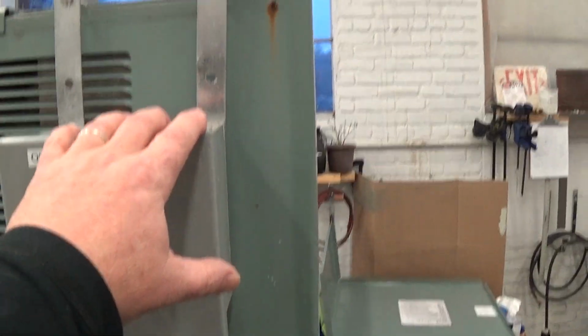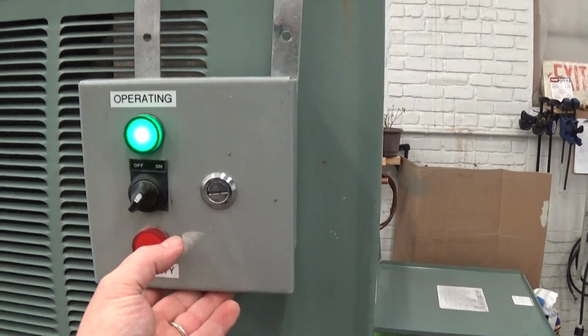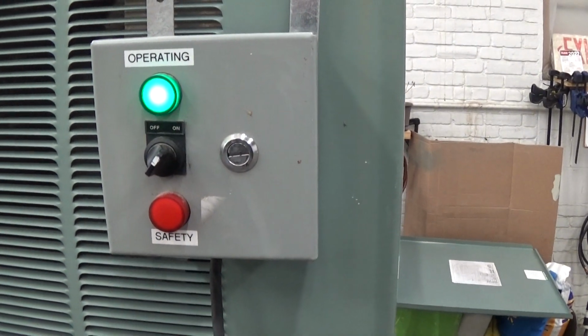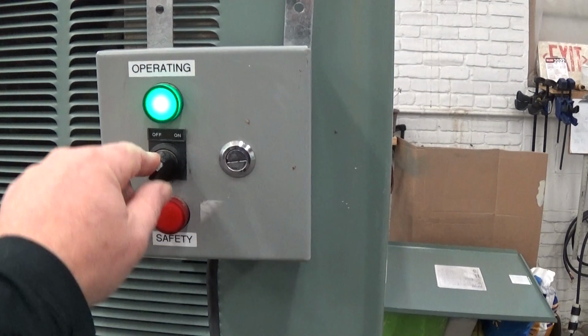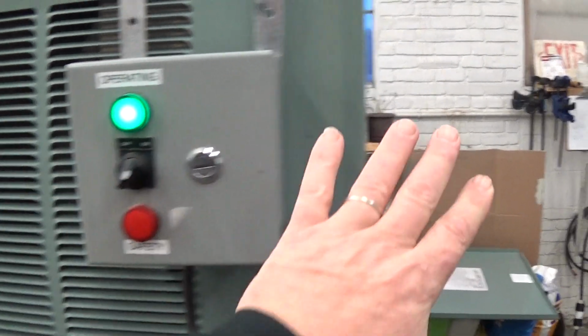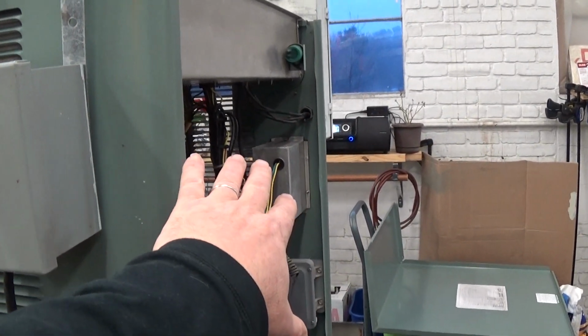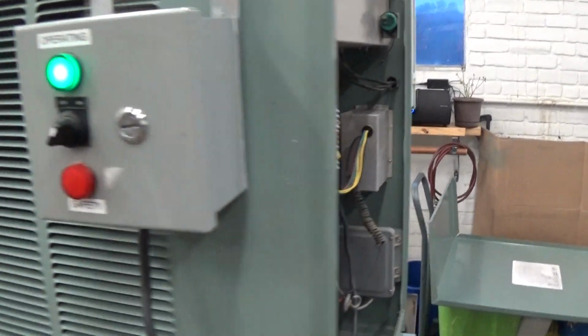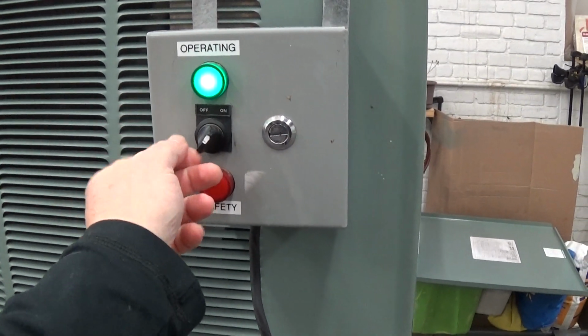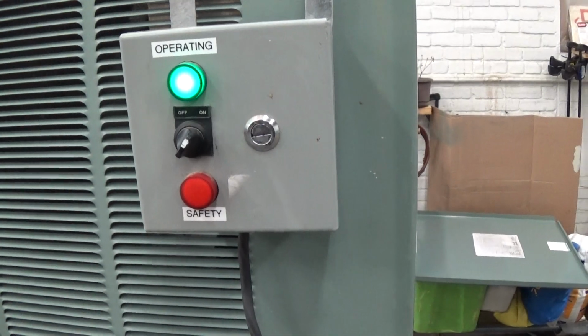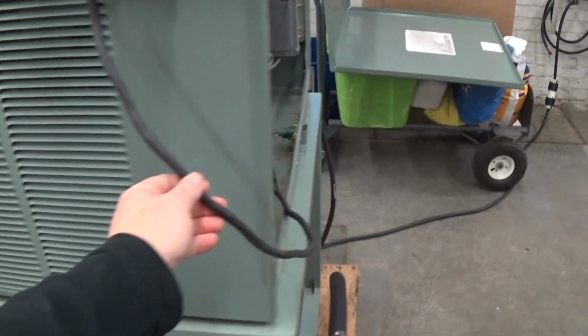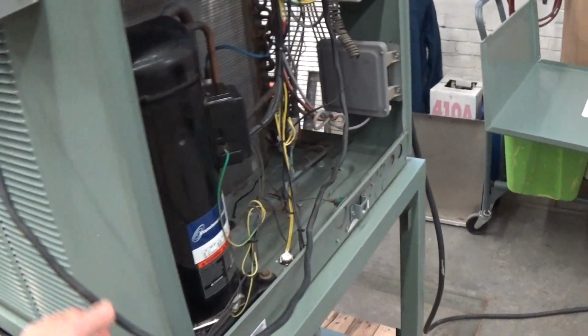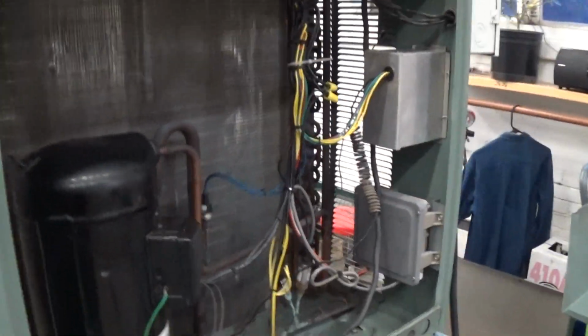Now this unit, not all of them have it, has a little remote panel that you can bring indoors. We just kind of have it hanging off the side here. That will ship in a box. And with that, you can leave the chiller just on the cooling cycle there, and you can just perform your off-on if you want to run this cable in the building. The cable it currently comes with right now is fairly short, and let's see how many conductors that is. I think it's 5.